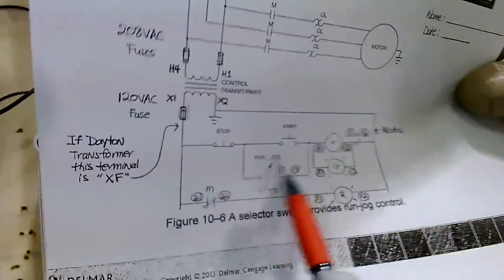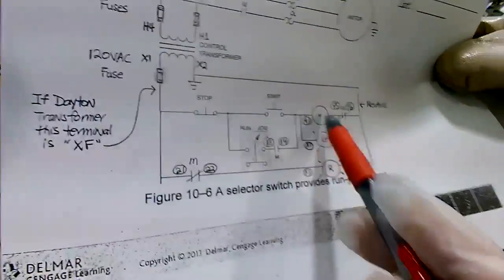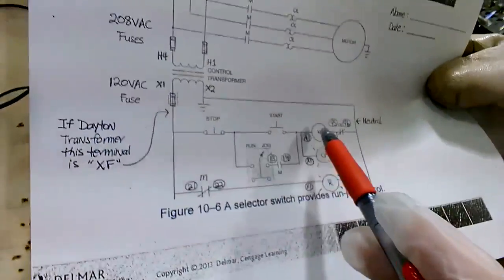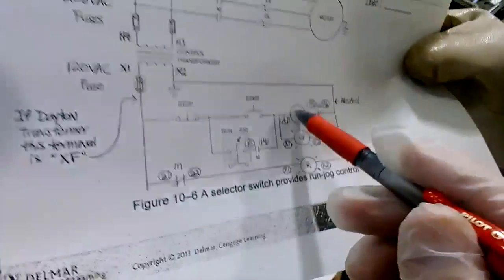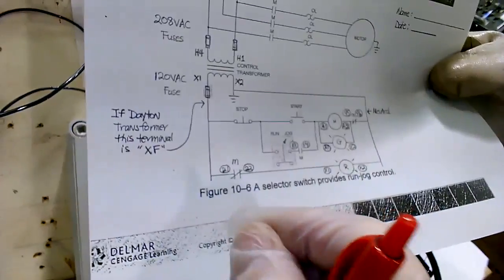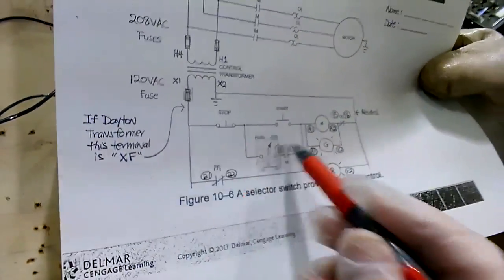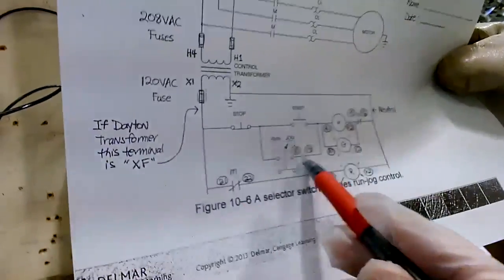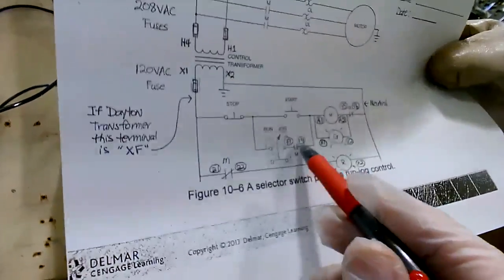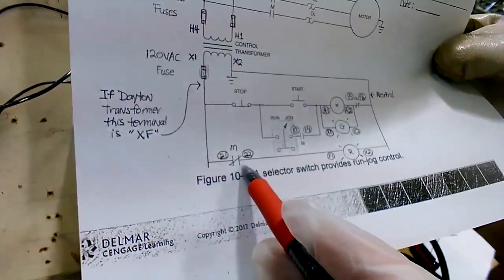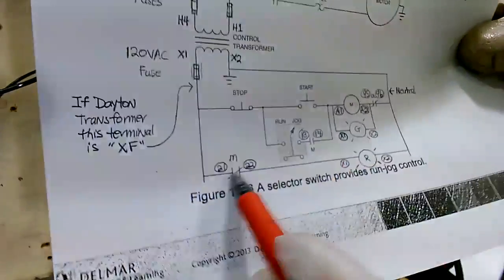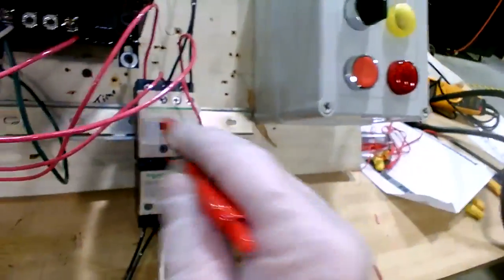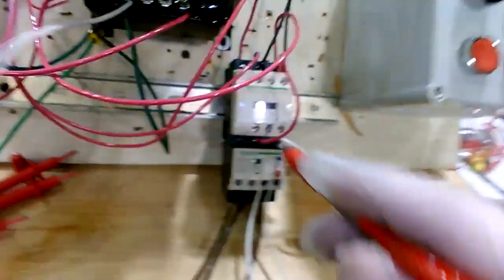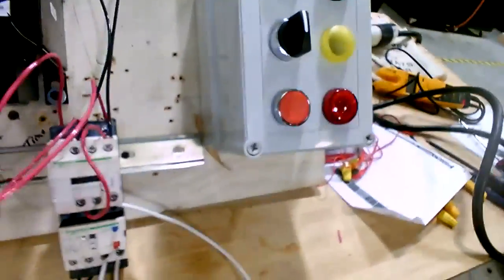The holding contact that you have here is already wired. It goes in line with this. When that coil comes on, that closes. But that coil will make this one open. When that coil comes on, it's going to make the top open. When that coil is de-energized, this will be closed. So the holding contact and this one are always going to be opposite. Always opposite. If that's closed, that'll be open. If this is open, that'll be closed. Normally open, normally closed, and they're both M and they're both controlled by the coil, side by side here. So that's going to be your indicator for that red light.